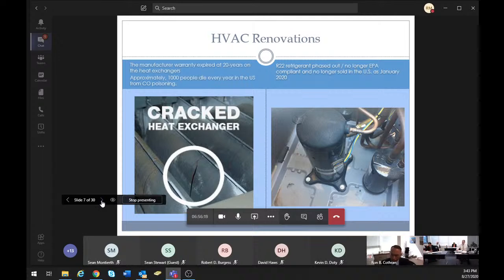This slide not only pertains to the previous slide about heating and air conditioning, but all future slides within my presentation that are about heating and air conditioning. The manufacturer's warranty on a heat exchanger is 20 years. Please look at the picture on the left. The heat exchanger is a thin gauge steel that expands and contracts when the system heats up and cools down. With expansion and contraction over time, this causes the steel to weaken and crack. When the heat exchanger has a crack, it will leak carbon monoxide, also known as CO, into the occupied space. CO is a gas which can cause headaches, nausea, dizziness, breathlessness, and death. Approximately 1,000 people die every year in the U.S. from CO poisoning. The picture on the right shows a typical compressor that uses R22 refrigerant. R22 refrigerant is no longer EPA compliant and is no longer sold in the U.S. as of January 2020.